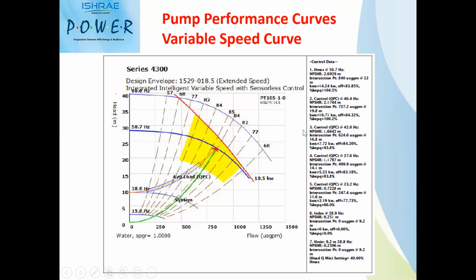So this will give you complete details at what flow, what head, what frequency a pump is operating. So these data are used for calculating our part load power requirements, part load efficiencies for the complete plant equipment. So whenever you are selecting a pump, if it is a variable speed application, please make a note of this variable speed load details also.